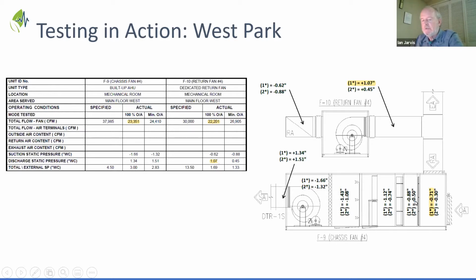So the purpose of this little story is just one example of one system in an older facility and a few of the things. Then we could run through the same thing on the minimum outside air. When these tests are done by a capable contractor and you read the results, they lead directly to typically maintenance actions and control adjustment actions that can resolve comfort problems as well as significantly lowering energy use.